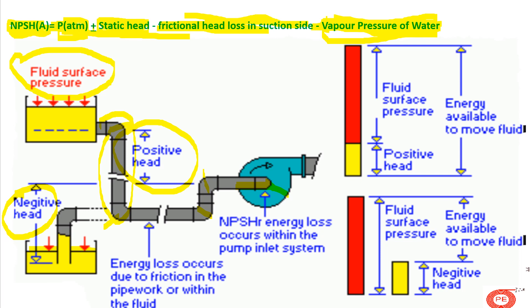As I mentioned in part 1, NPSH available must always be greater than NPSH required — only then will the problem of cavitation be stopped. Otherwise cavitation will persist in the pump and the pump will not work properly, leading to malfunction. I hope you now understand net positive suction head calculation. Please like, follow, and subscribe to our channel, and let us know in the comments if you have any queries or feedback. Thank you for watching.